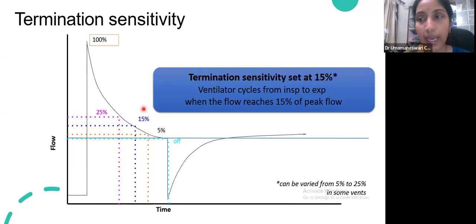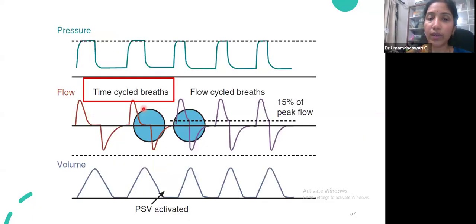Many of the machines will not even ask for a termination sensitivity. It is fixed already at 15%. So here, this is a time cycled breath. You can see that after the flow is completed and comes to the baseline, the machine is still in the inspiratory phase only. Here you are changing from time cycled to flow cycled breaths, where you have set a termination sensitivity of 15%. When the flow reaches 15% of the peak flow, the machine automatically switches over from inspiration to expiration, thereby giving more control to the baby.